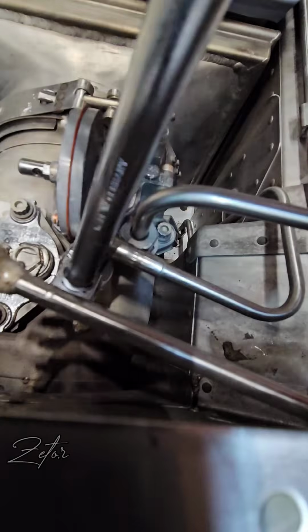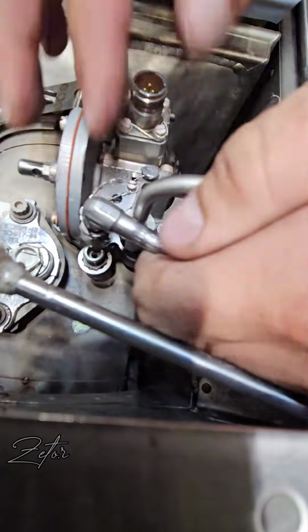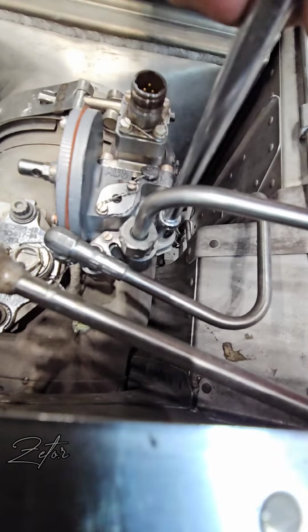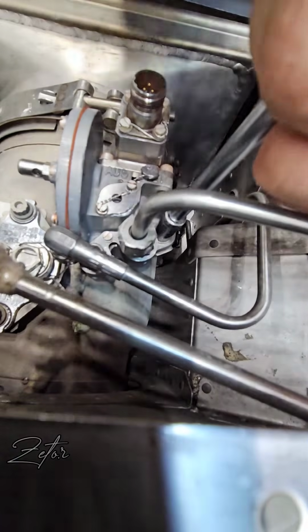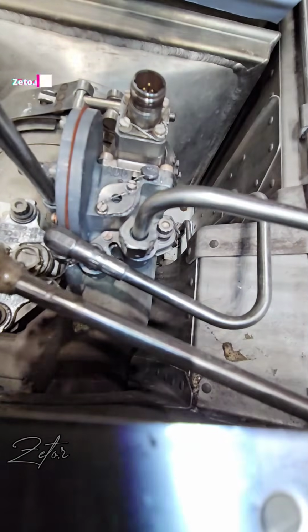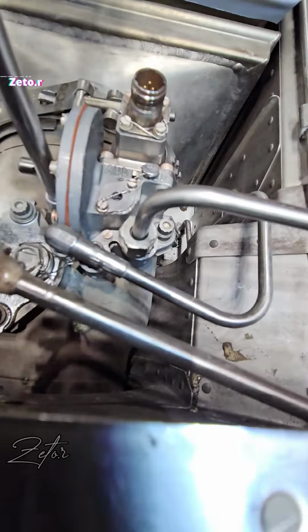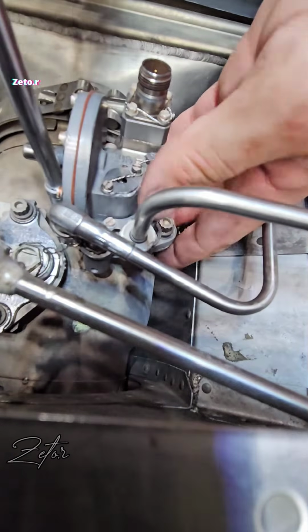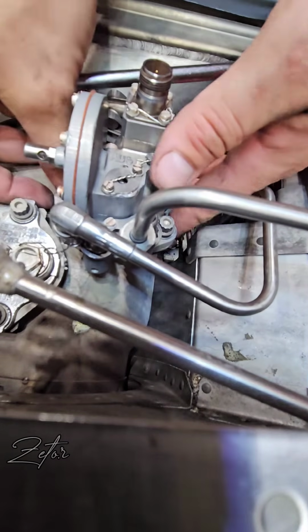Let's start with the pneumatic mode. It is here to prevent reverse flow. Here's how it works: the PRV closes when a delta pressure between the precooler outlet and the PRV inlet is detected. This mode works automatically with the help of the diaphragm inside the control solenoid.